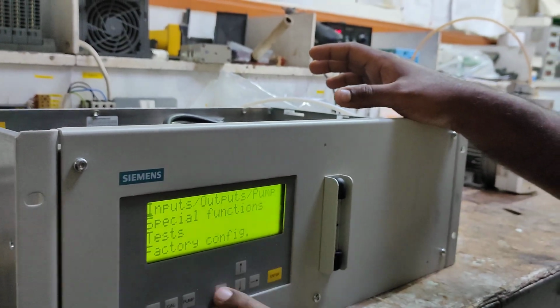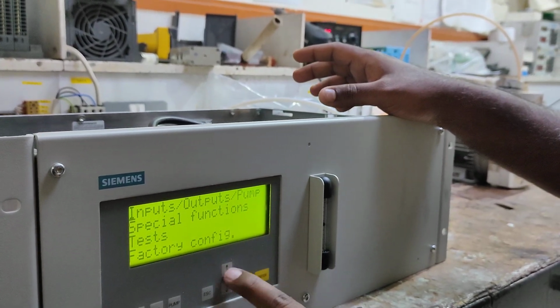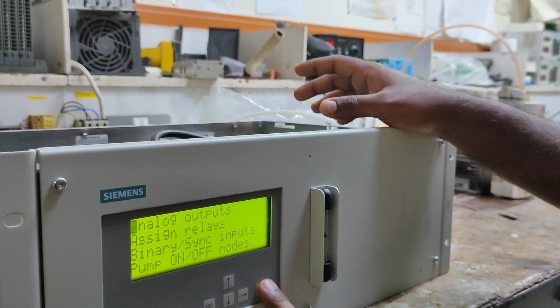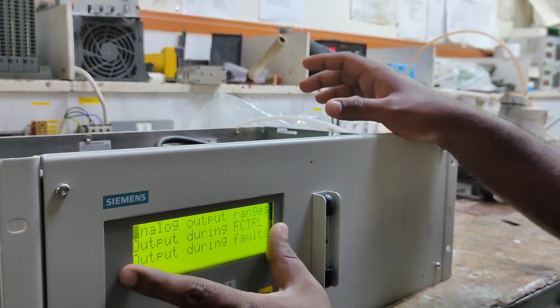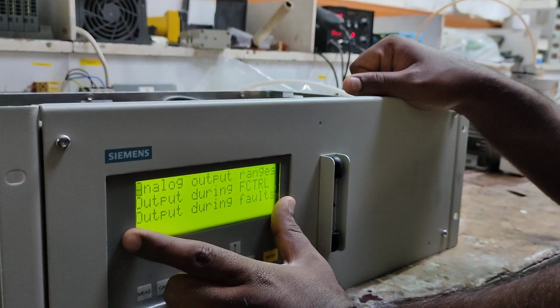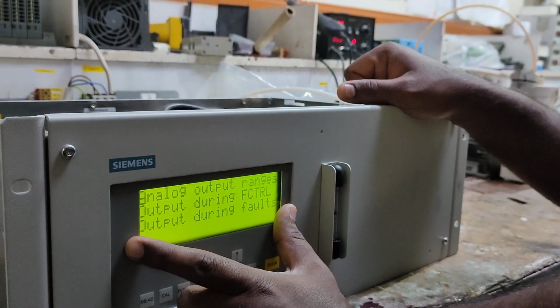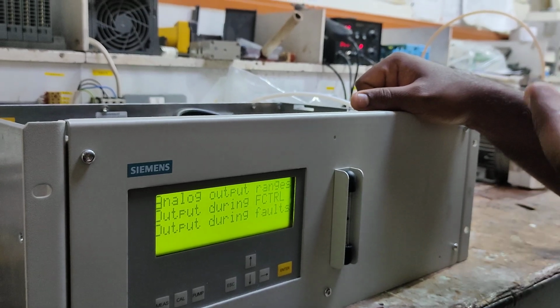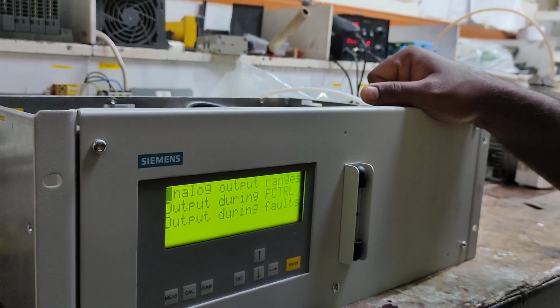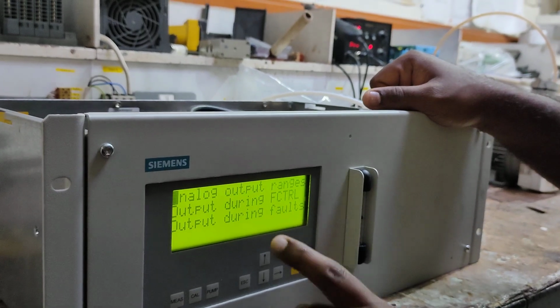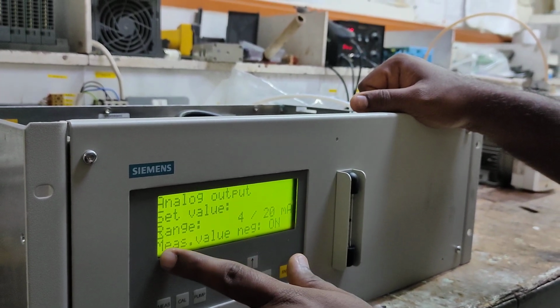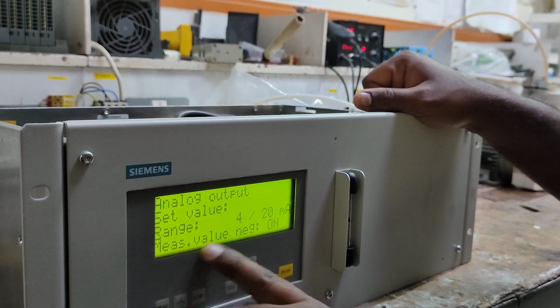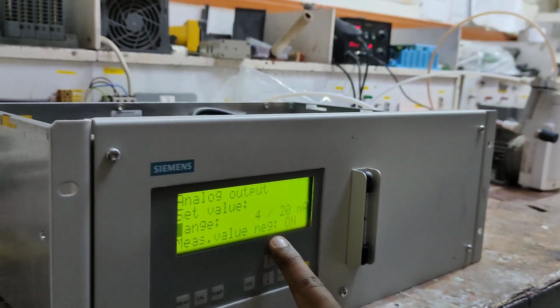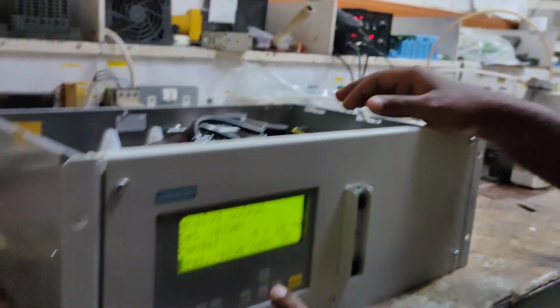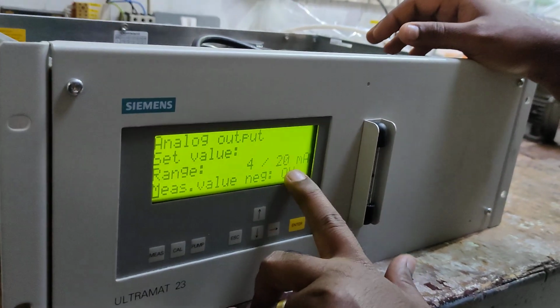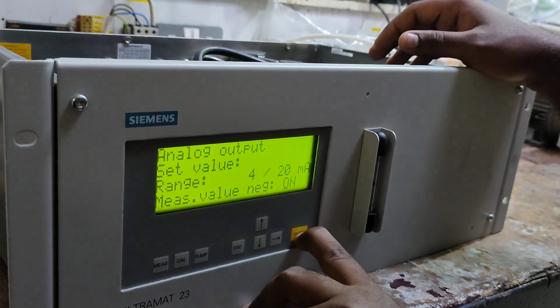Okay, so we are at configuration, input output, analog output, ranges. Here you set how the analog output should react when it is in fault condition, hold condition, or auto zero condition, because you should not report any wrong value to the DCS. First, do you want to measure negative values or not? If the value goes negative, the loop current should not go less than 4. It should stay at least at minimum 4. So with measure value negative on, you switch it off.